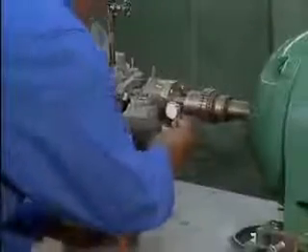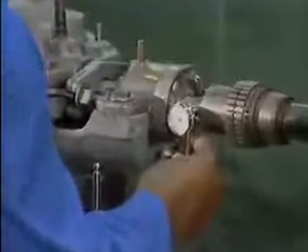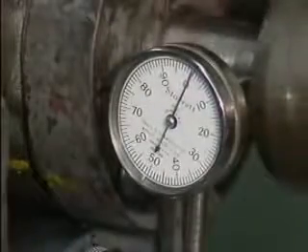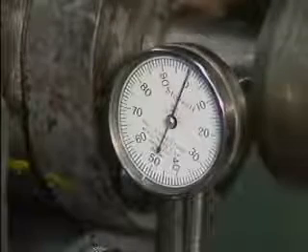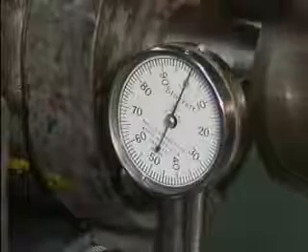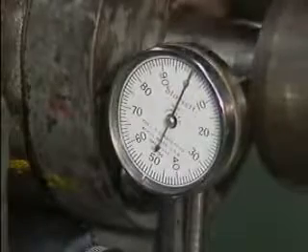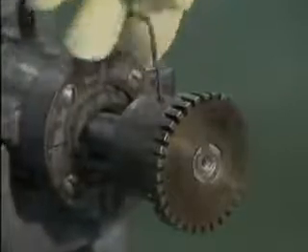One way to narrow down the cause of the problem is to take another set of run-out readings with the dial indicator stem contacting the shaft. If those readings are within the acceptable limits, the problem is likely to be a defective coupling hub. But if those readings are also excessive, it's likely that the bearings are bad or the shaft is defective. Whatever the problem, the necessary repairs will have to be made before an acceptable shaft alignment can be achieved.